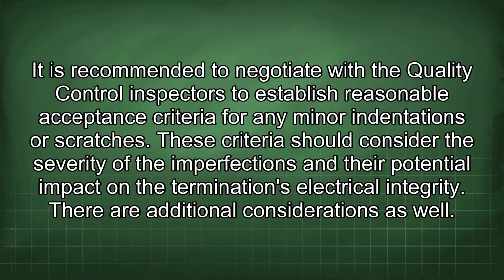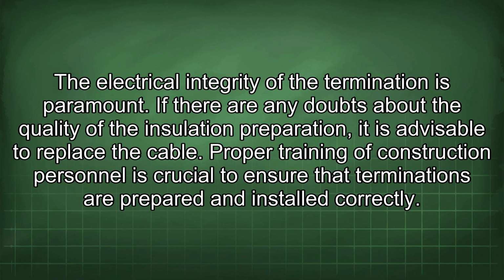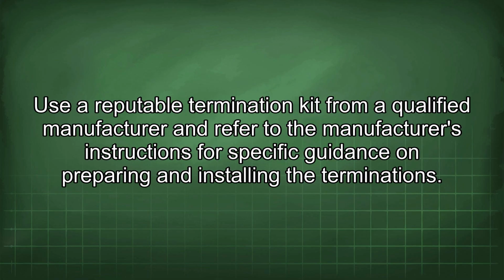There are additional considerations as well. The electrical integrity of the termination is paramount. If there are any doubts about the quality of the insulation preparation, it is advisable to replace the cable. Proper training of construction personnel is crucial to ensure that terminations are prepared and installed correctly. Use a reputable termination kit from a qualified manufacturer and refer to the manufacturer's instructions for specific guidance on preparing and installing the terminations.